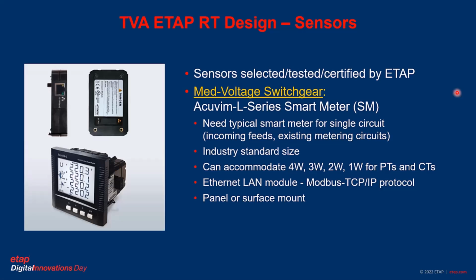Now let's talk about the specific sensors that we'll be using. For our medium voltage switchgear, the sensors that we selected, and they were tested and certified by ETAP for this application, are AccuVim L series smart meters. And these are typical smart meters. You can think of them that way, that you would use in a single circuit application. And in our case, we're using it for the incoming feeds. And like I said, we're going to piggyback over our existing metering circuits.